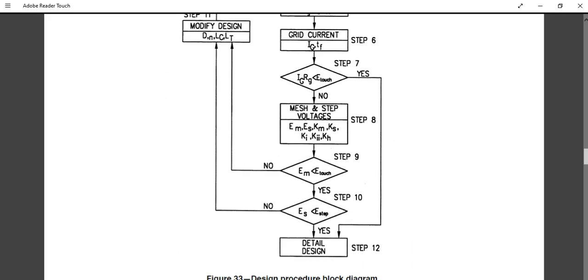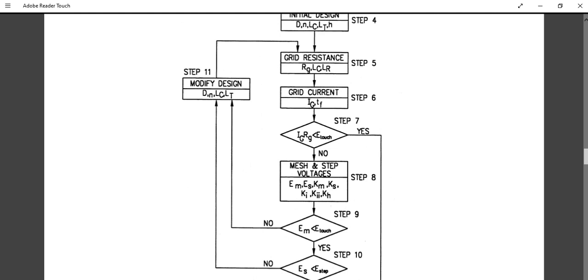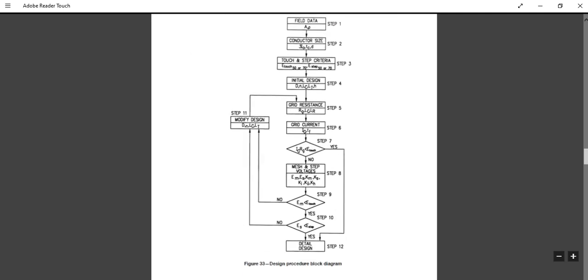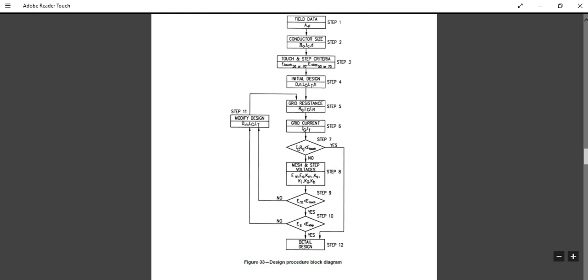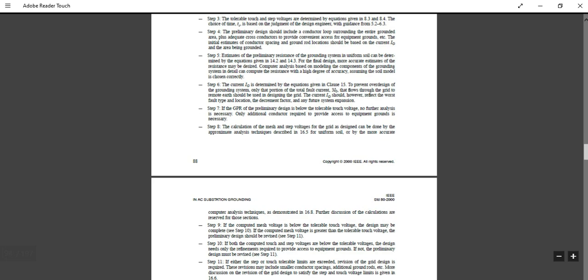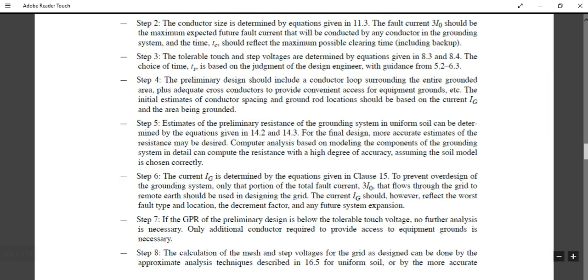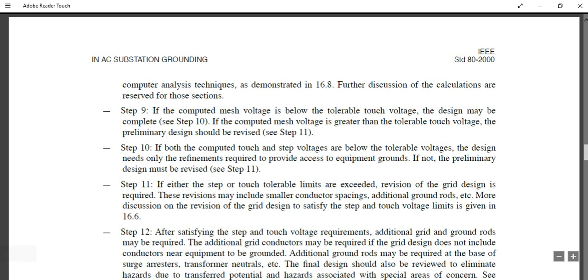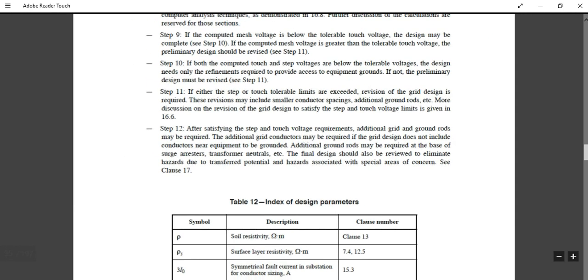This is the algorithm based on which you design the ground grid. ETAP software uses this same IEEE 80 algorithm to calculate the ground grid design — I have prepared a video on that as well. To summarize the steps: Step 6 is IG, Step 7 is GPR (ground potential rise), Step 8 calculates mesh and step voltage, Steps 9, 10, 11, and 12 complete the design process.